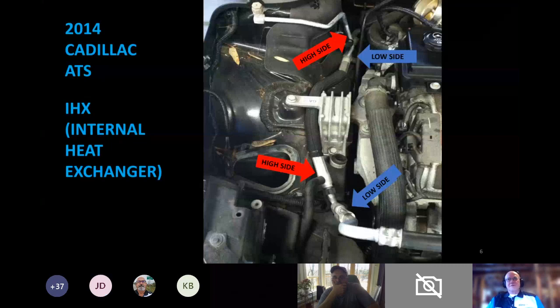Rick, do you have any idea if that is true? And Dan from chat said, just to recap, the purpose of the IHX is to ensure all liquid is turned to gas before entering the compressor. It is an efficiency tool to do exactly that. We're using the heat from the high side liquid refrigerant to heat up the remaining droplets of vapor in the outlet of the evaporator to make sure that there is nothing but vapor, warm vapor, coming out of the IHX and into the compressor. It is an energy saving device.